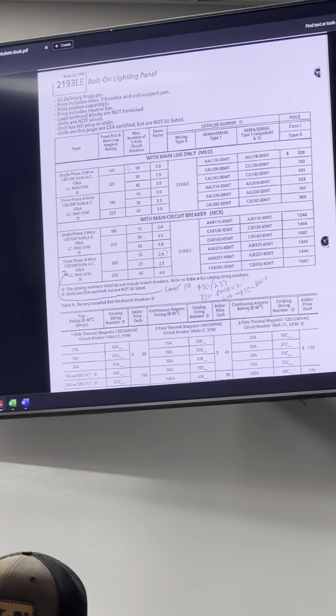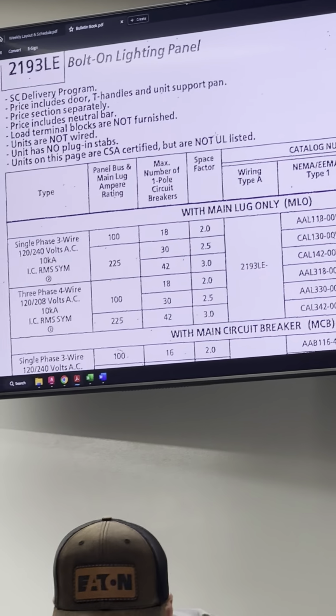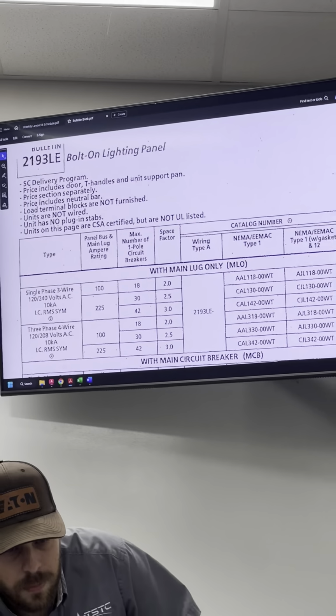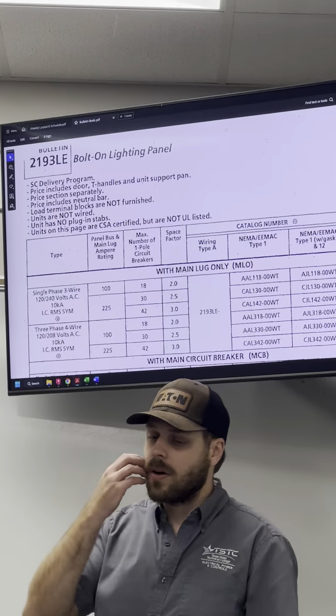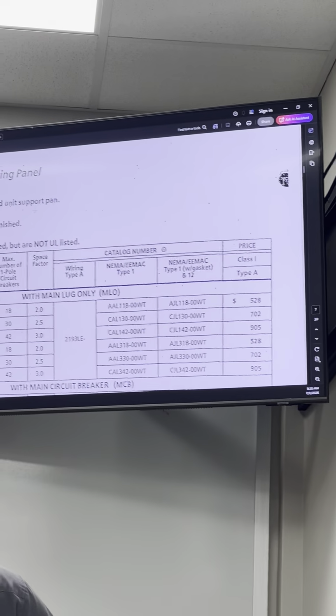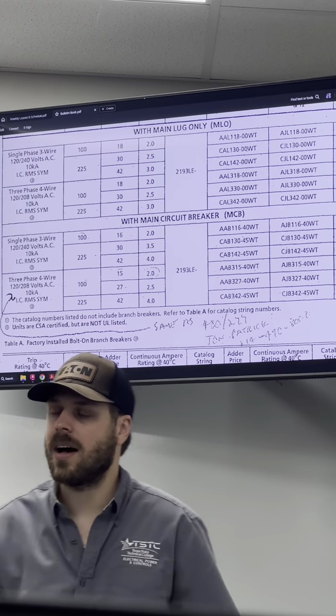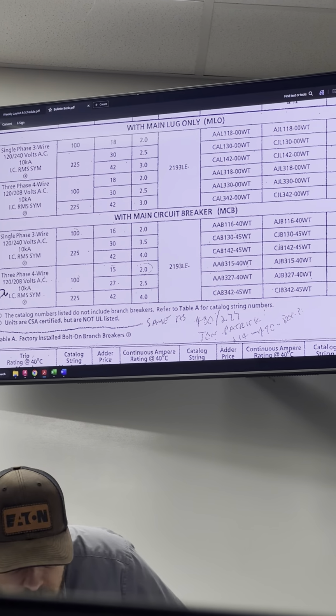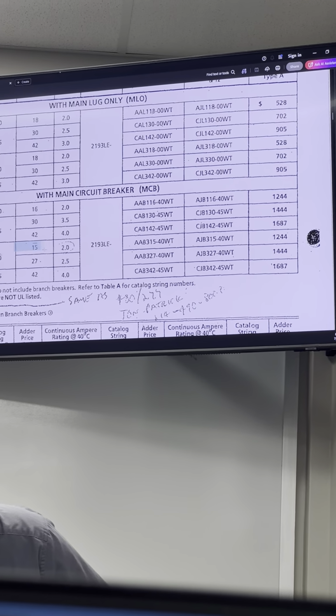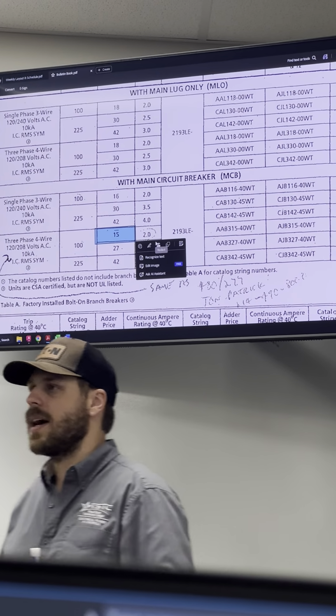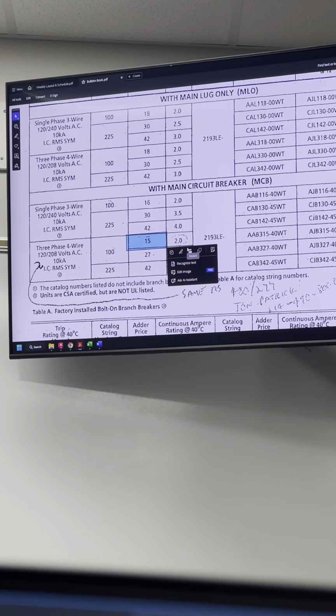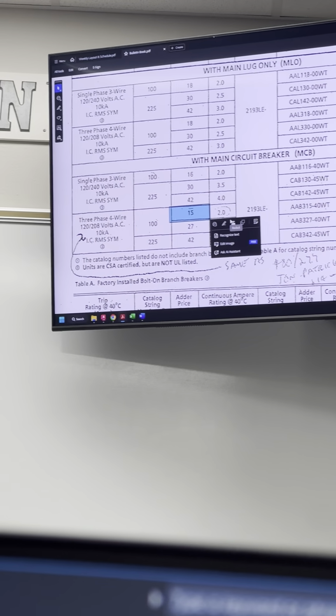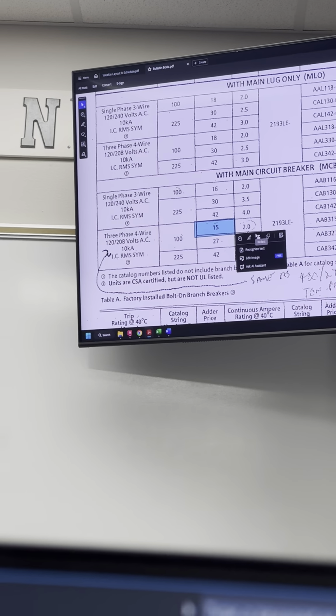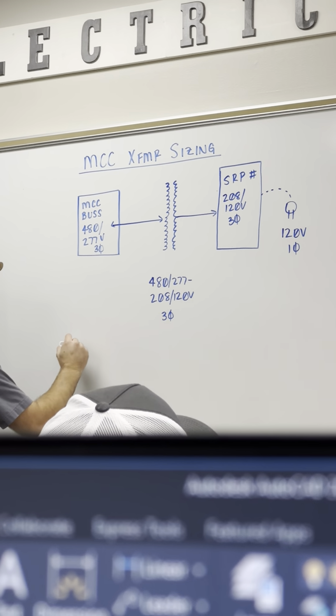So, the first thing we'll look at here is in our bulletin book. We actually looked at this page. This is page 7, by the way, if you want to follow along on your screen. But we looked at this bulletin 2193 LE a couple weeks ago whenever we did our lighting circuit in the shop. It's the exact same panel that we're using to house all of our receptacle panels. So we chose this one down here at the bottom. It says that it can hold 15 circuits here, but by the time you lay it out, that's where you get that 16 circuits. So again, going back a few weeks when I told you all shop receptacles, make sure you only had 16 arrows pointing back to each MCC.